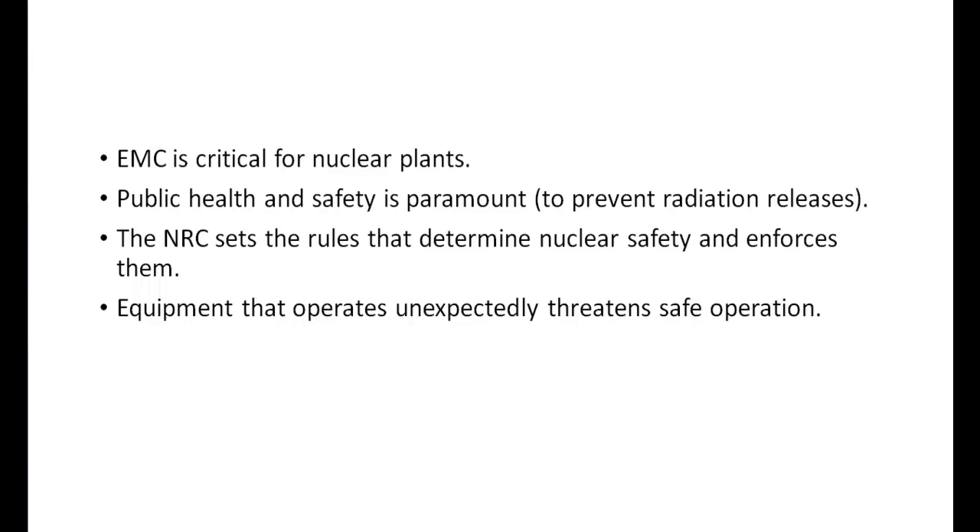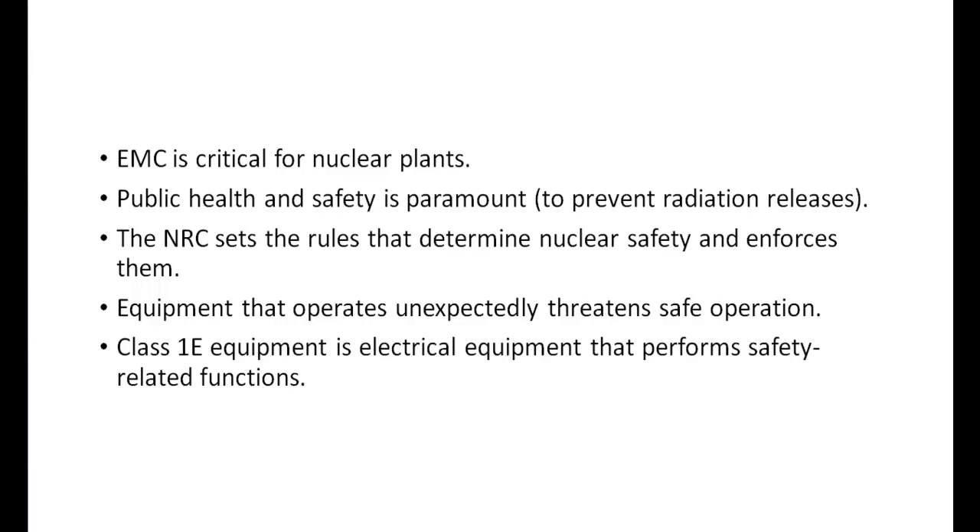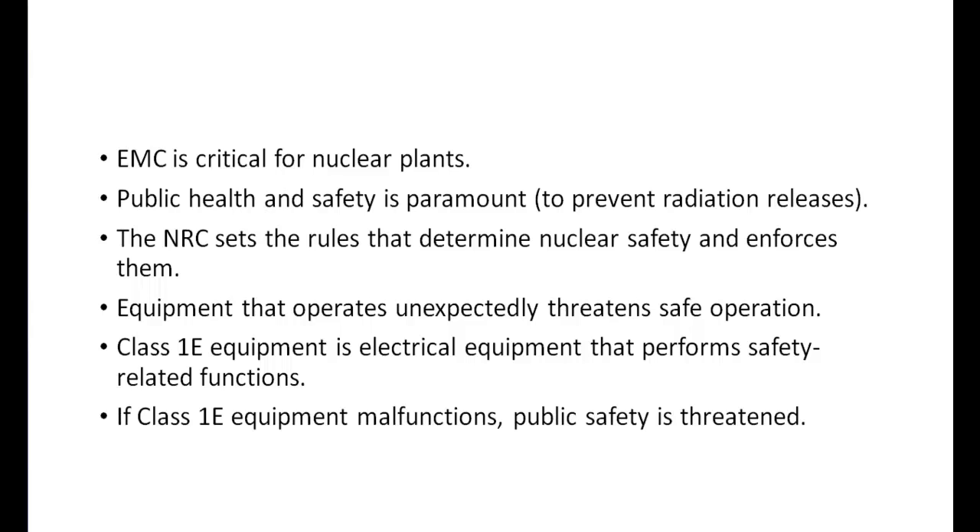Some electrical devices are more critical than others. Class 1E circuit breakers, for example, perform safety-related functions — they are intended to isolate non-safety-related power from safety-related power. Their purpose is to enable the smooth and uninterrupted operation of critical safety-related equipment by guarding against disturbances created by non-safety-related equipment. But if their function is interfered with by nearby electronic equipment, this protective role can be defeated, and with it a major pillar in the NRC's regulatory strategy for keeping the public safe from accidental radiation releases.